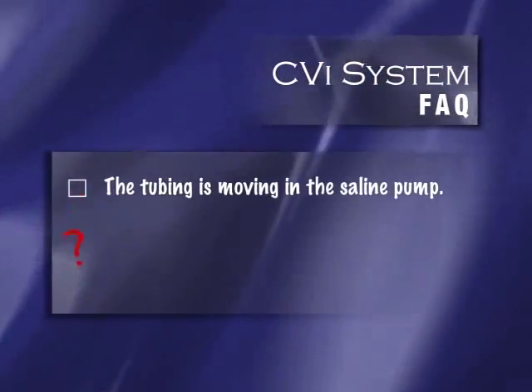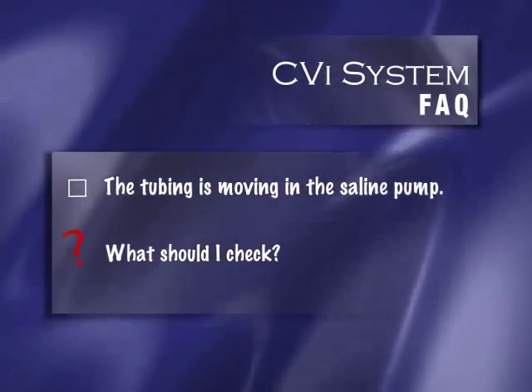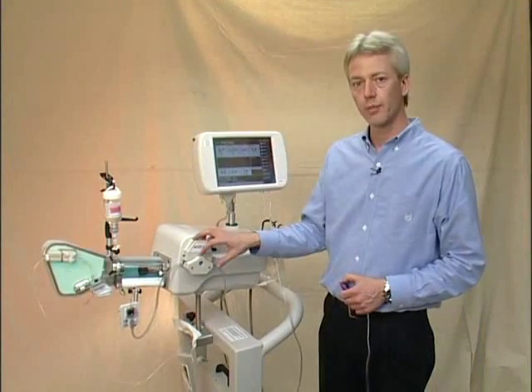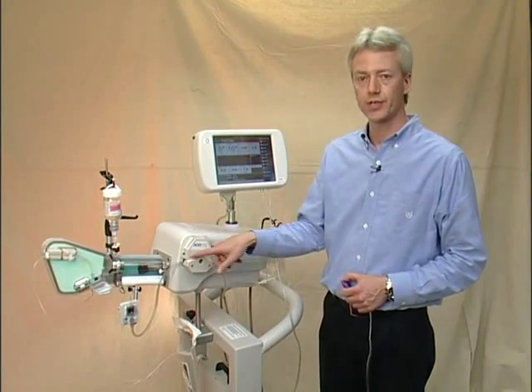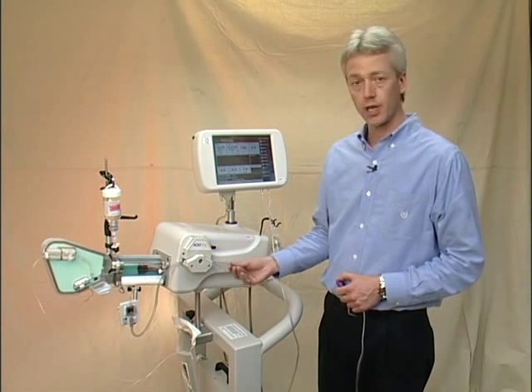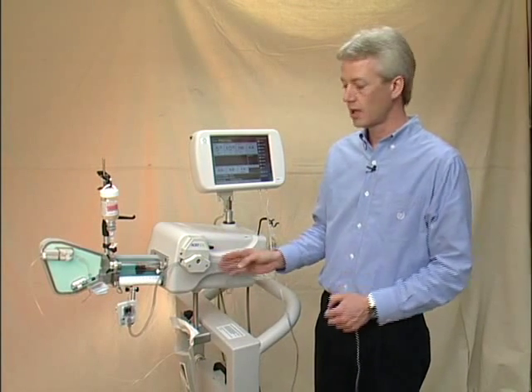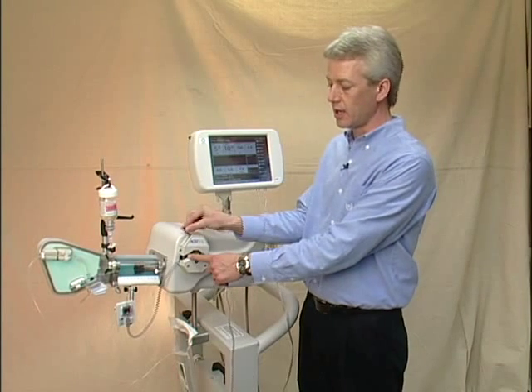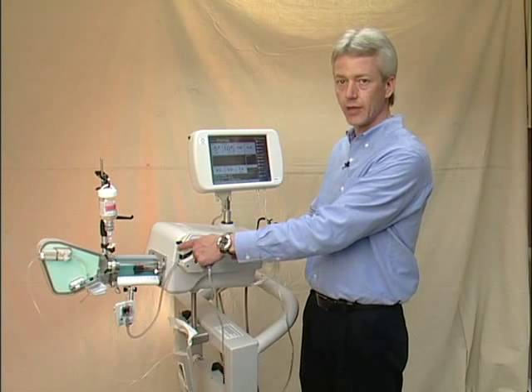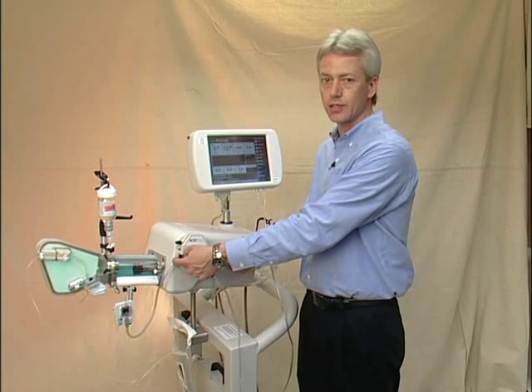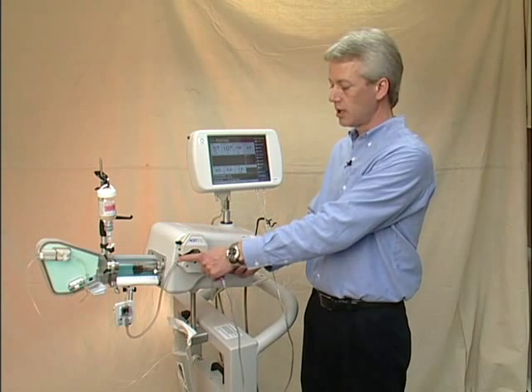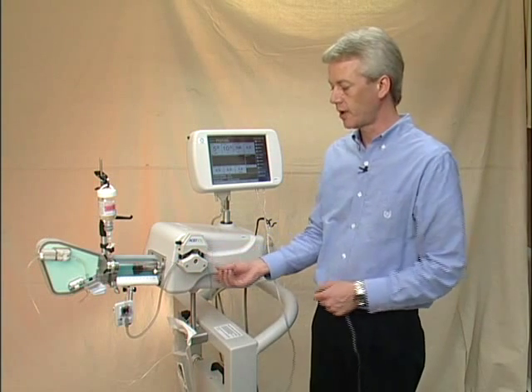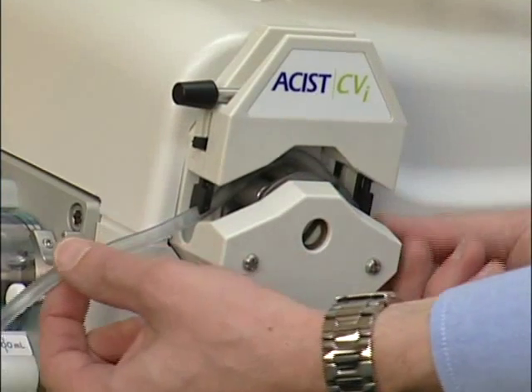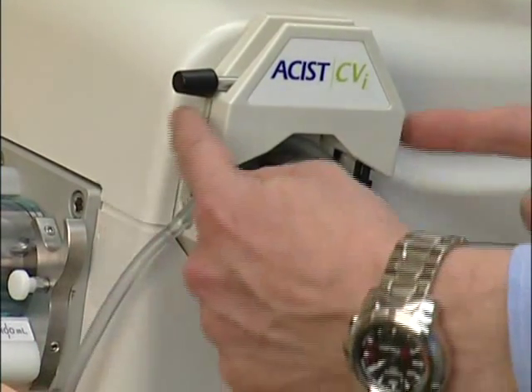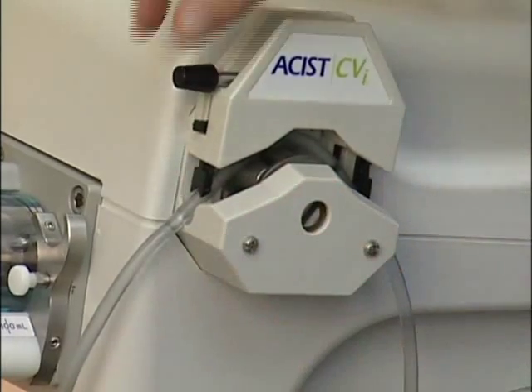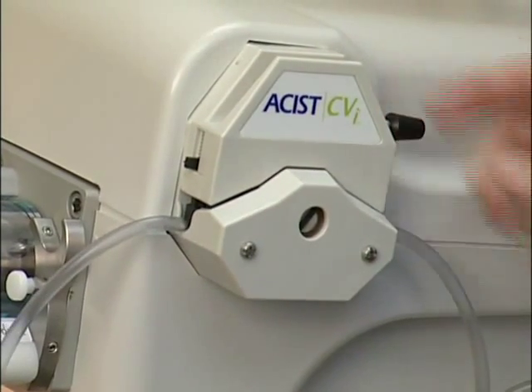The tubing is moving in the peristaltic pump. Why is that? The peristaltic pump roller assembly is designed to accommodate different size tubings. Our saline tubing is a standard size, and so the guide teeth on the peristaltic pump should always be in the down position and locked. If that's not done, it's not pinching the tubing hard enough and allows the tubing to walk through the system, as we say. Ensure that those black tubing guides are in the down position and the latch is fully closed.